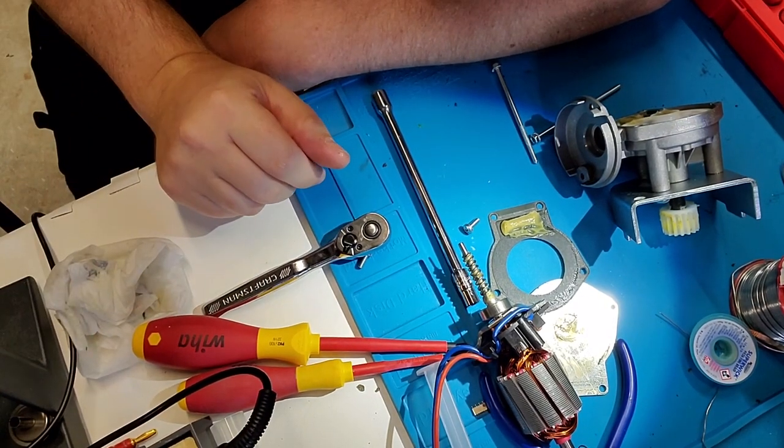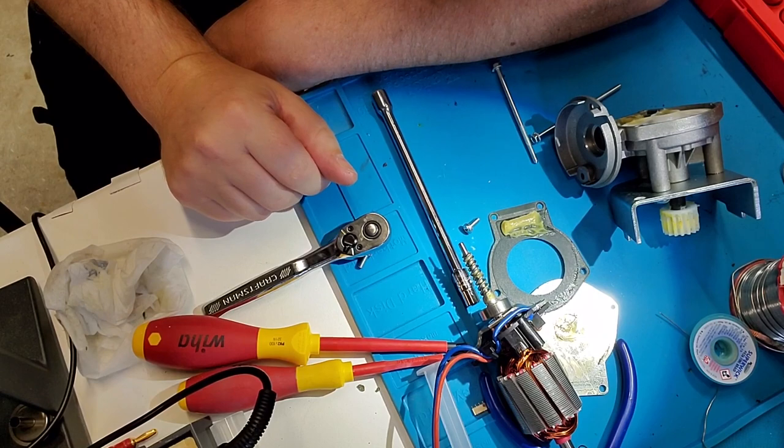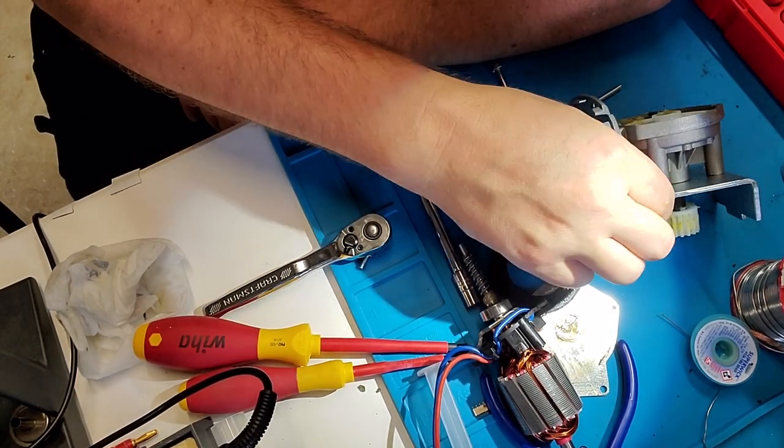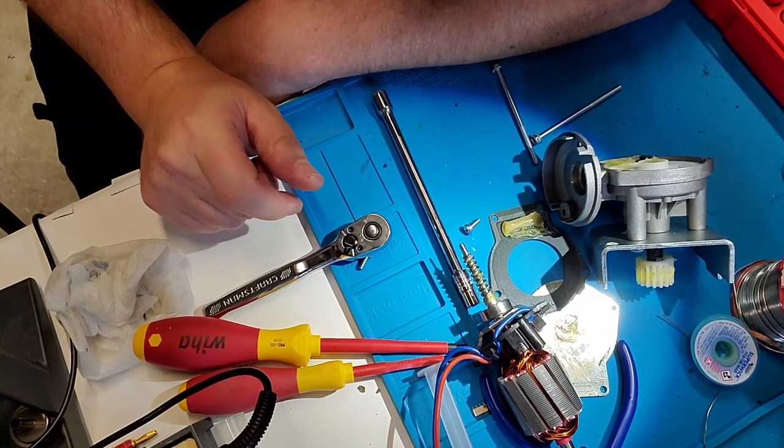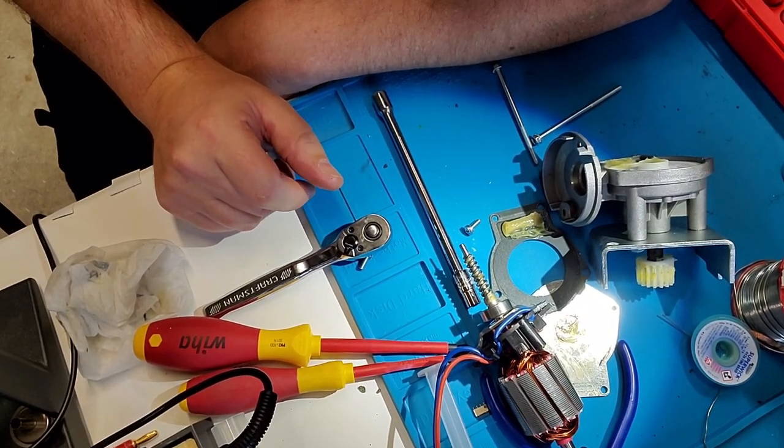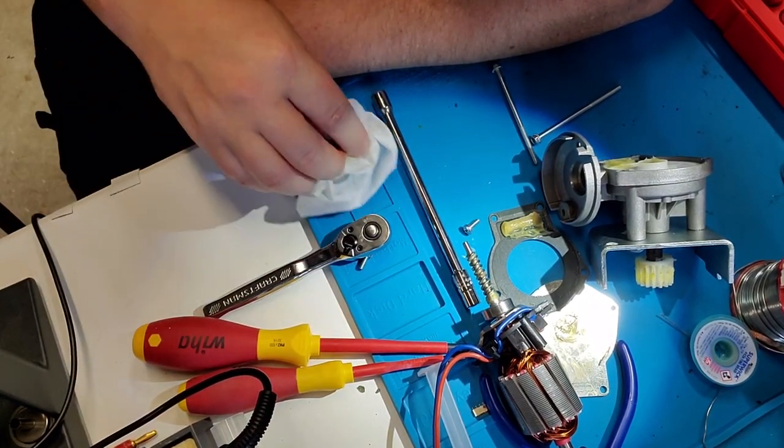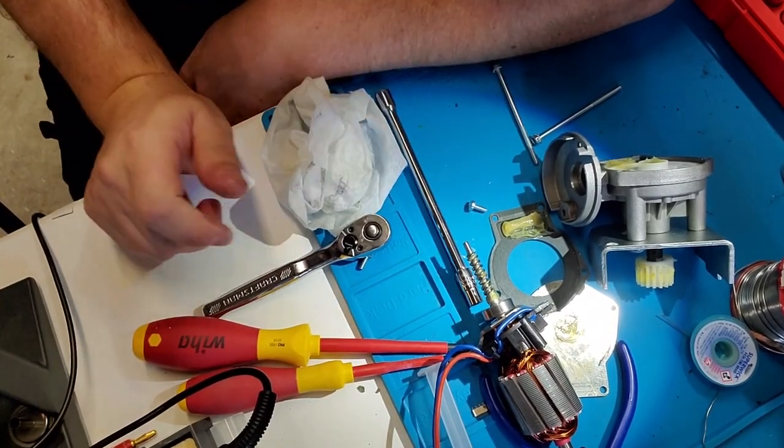Normally, if there's some sort of breakdown, you'd see it right there by the brushes or you see metal flecks appear in by the stator magnets. But you don't have any of that. This motor is absolutely fine. This is just another case of somebody ordered parts that they didn't need. And here we are tearing it apart for your leisure because why waste it? I've already changed out the part according to what somebody said they needed. Two teardowns. I got a motor and a CPU out of a Medivator scope washer. Both units appear to be good or at least they're salvageable parts. So you don't just have to throw stuff away. We try and find another use for it somewhere further down the road. Thanks for watching, guys.